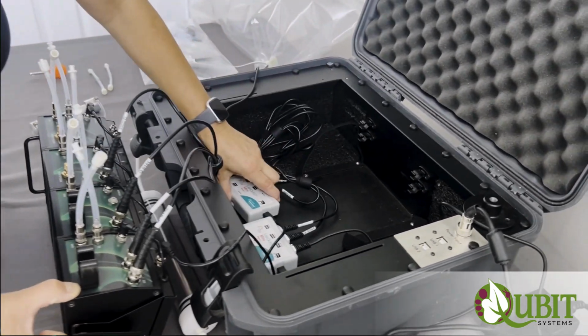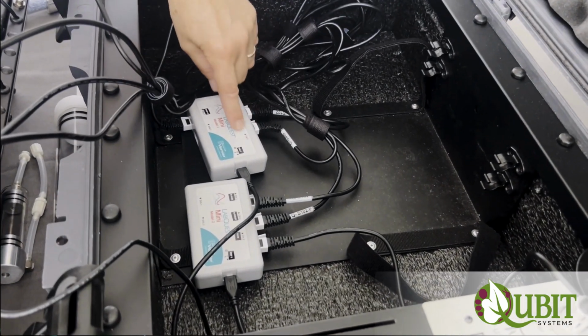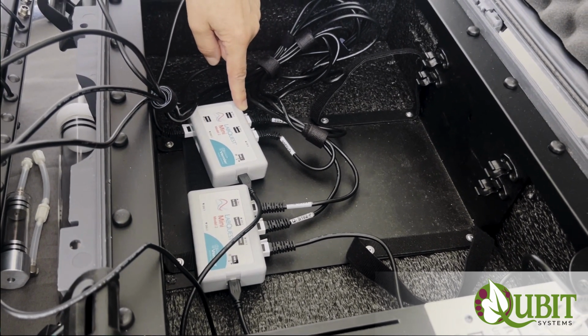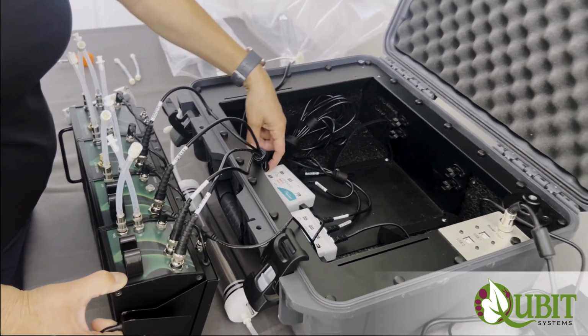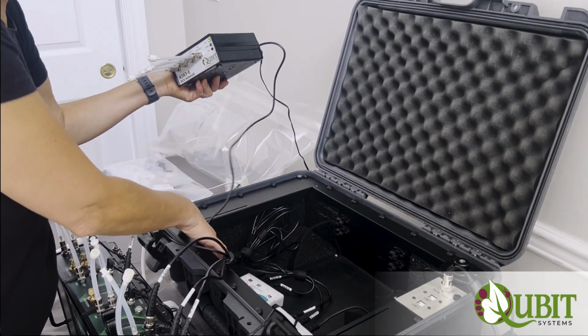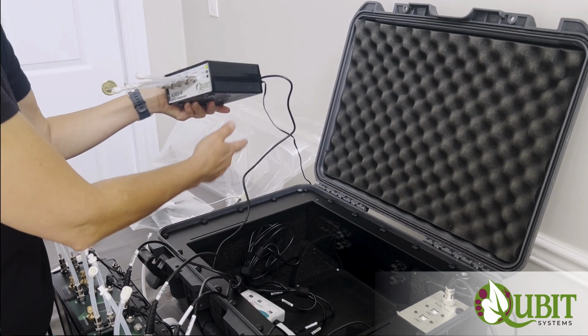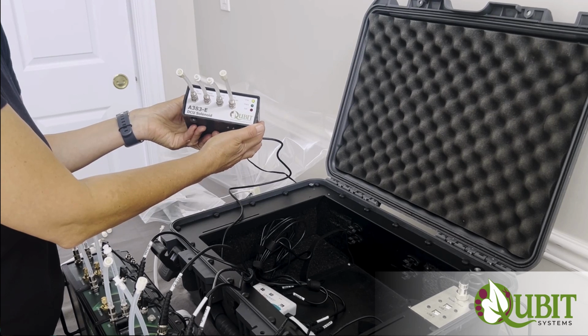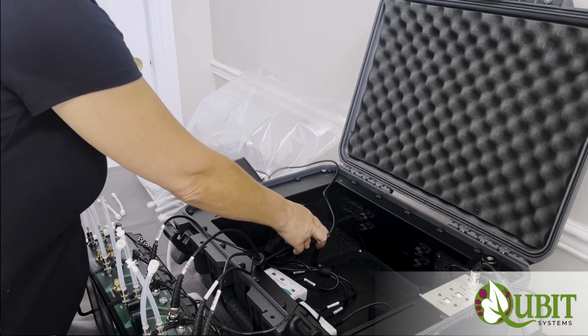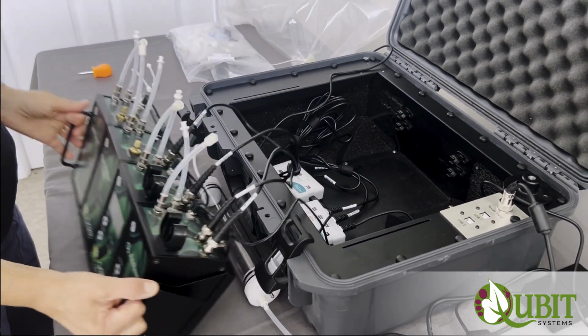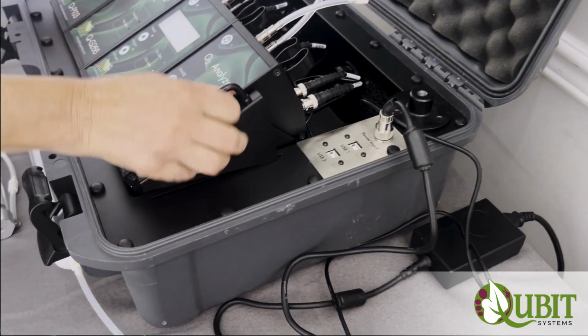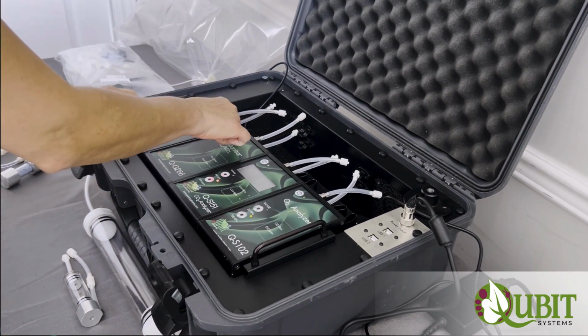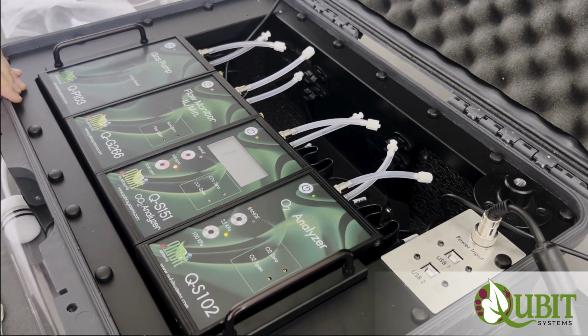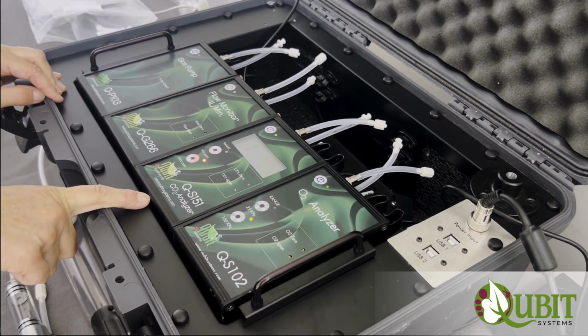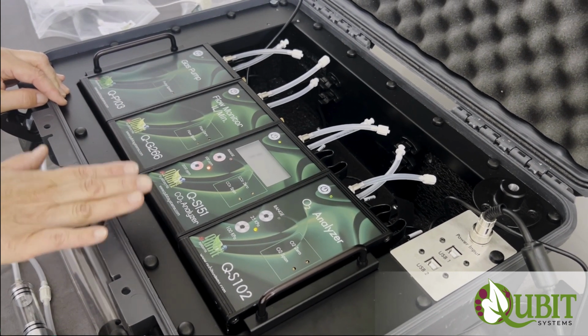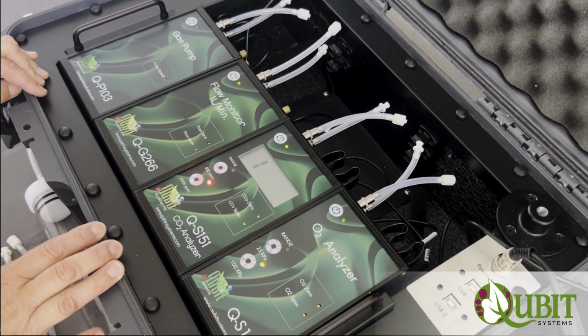These cables are connected to data interfaces, which are these LabQuest Mini interfaces. Each has 3 analog channels. They are labeled, so you know when you disconnect the sensors where to reconnect them. The DCU solenoid is connected to a Digi1 channel on the LabQuest Mini 2. And this DCU solenoid will control the flow of gas between reference and sample. So when everything is connected and ready, you can put the Q Box analyzer tray back inside, and you can power your analyzers and sensors. When you first power the CO2 analyzer, it needs to warm up, minimum 15 minutes, but half an hour is recommended. When the analyzer has warmed up, you will see the display showing actual CO2 values.